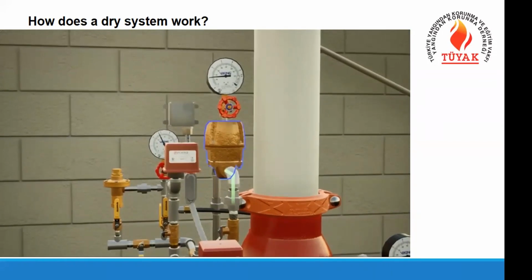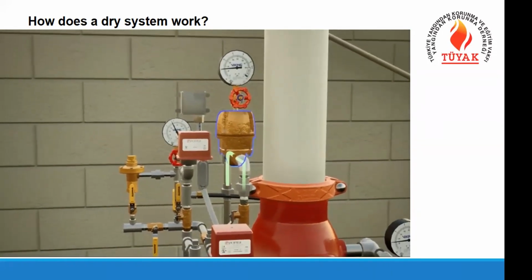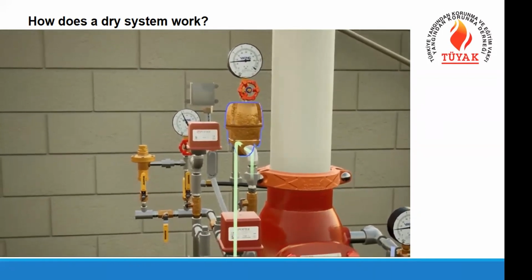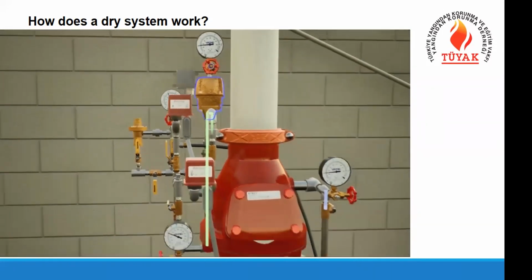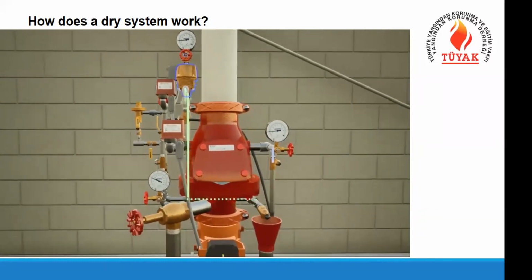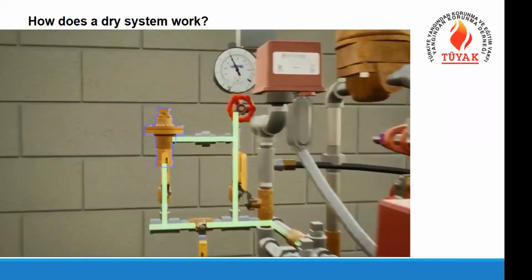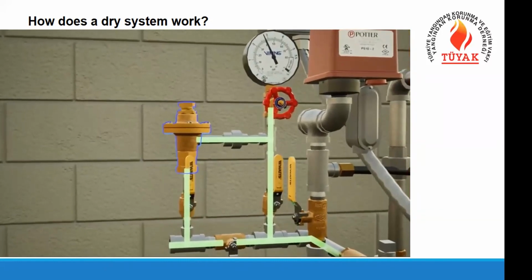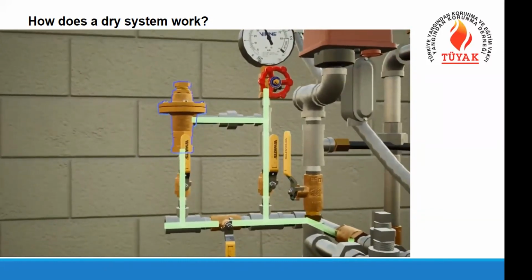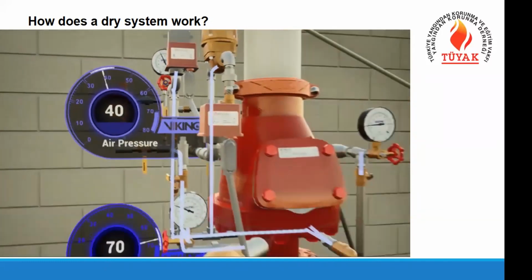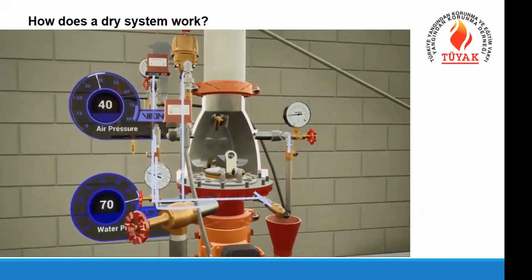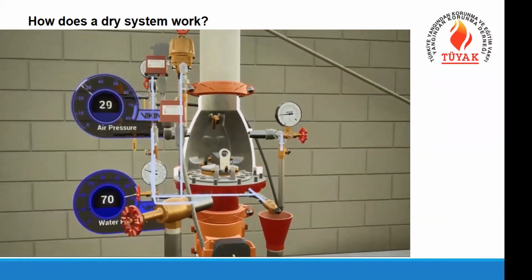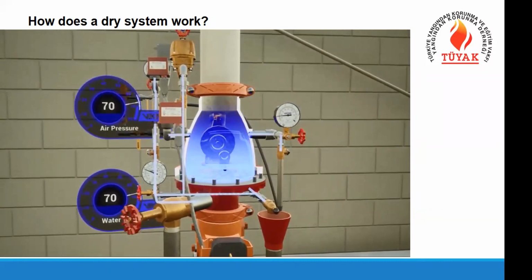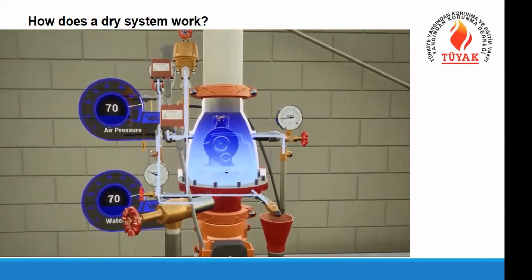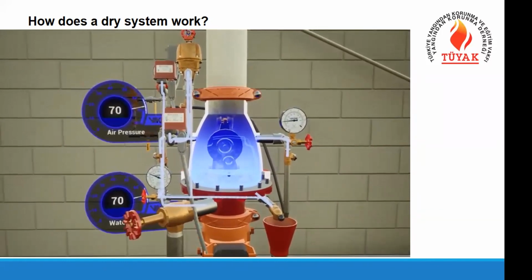If the system is equipped with an accelerator, a sudden drop of air pressure will cause the accelerator to activate, directing air pressure from the system side or outlet side of the dry pipe valve to the intermediate chamber of the dry pipe valve. If the air supply is equipped with an air maintenance device, air will pass through the air maintenance device to the system. As pressure reduces in the outlet chamber, the differential in the valve is equalized to a point that the remaining air pressure in the system cannot hold the clapper closed. The clapper is pushed open by the incoming water supply and then securely latched out of the way.